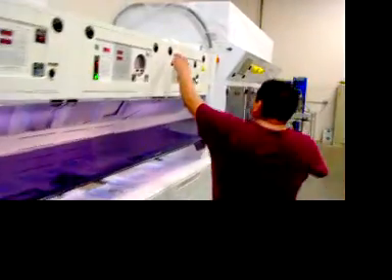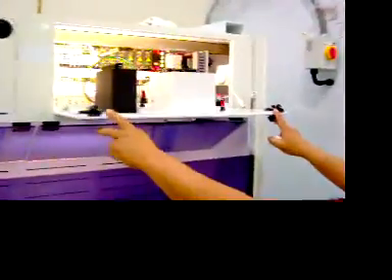Front EMO, rear EMO, loss of exhaust, front plenum full. There's a float switch right there. Float switch right in there. Rear plenum, right there, right in the corner there. And they are all going to a daisy chain and a safety relay.